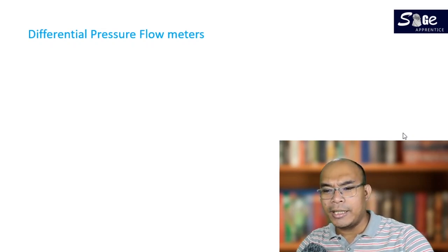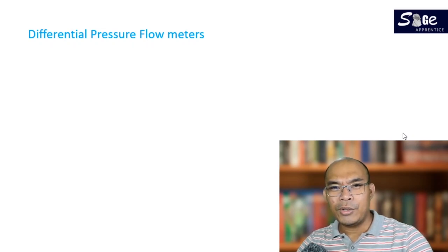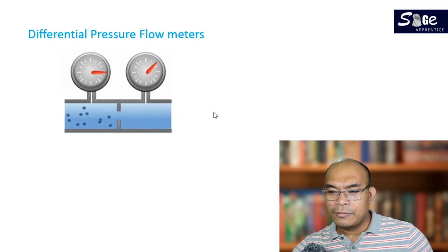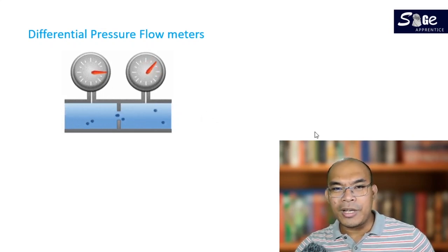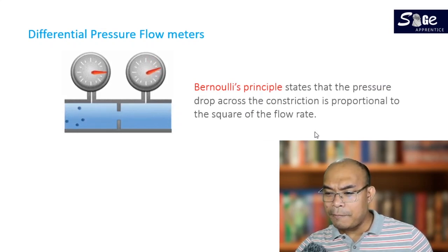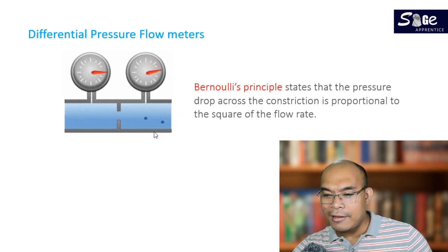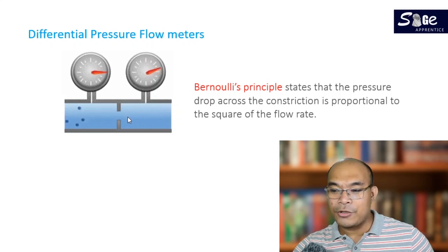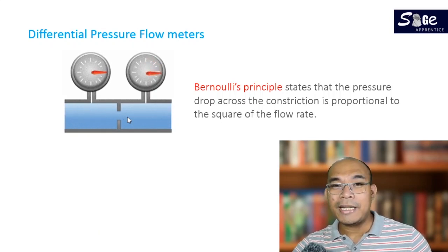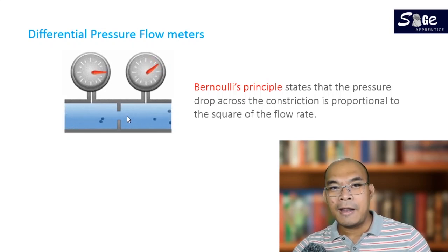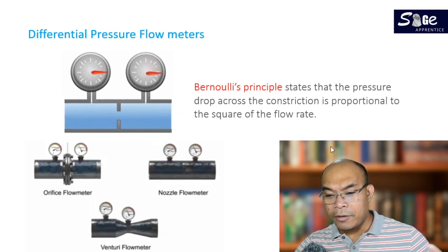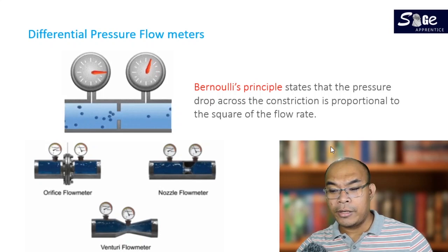The most commonly used flow meters are the differential pressure flow meters. The concept is that the difference in pressure will help us measure the flow in our particular system. This kind of flow measurement uses the principle of Bernoulli's, which states that the pressure drop across a constriction is proportional to the square of the flow rate. The most common differential pressure flow meters are the orifice, the nozzle, the venturi nozzle, and the venturi flow meters.